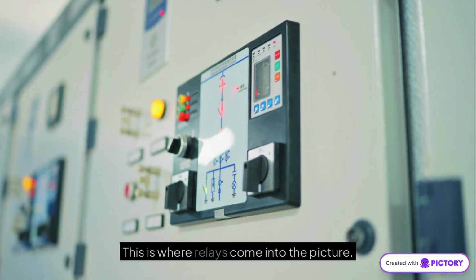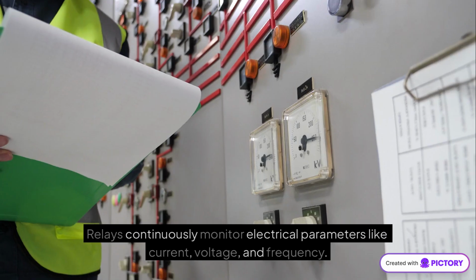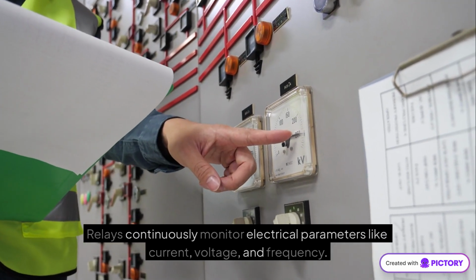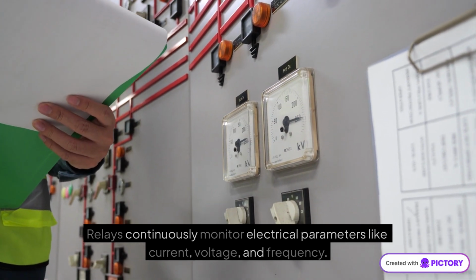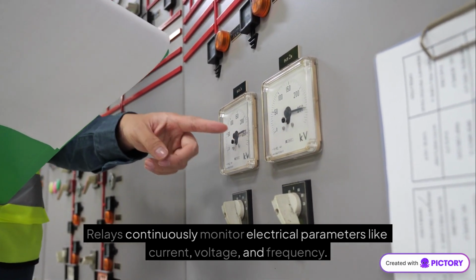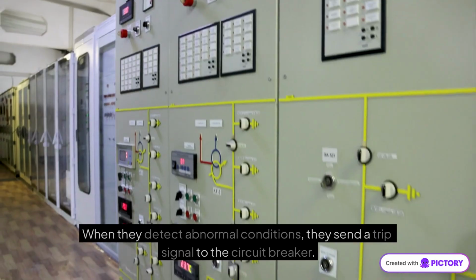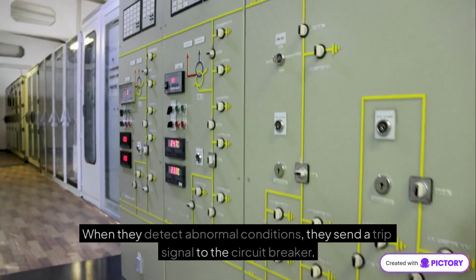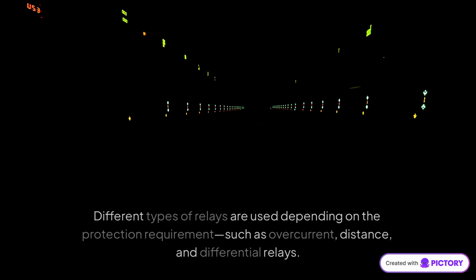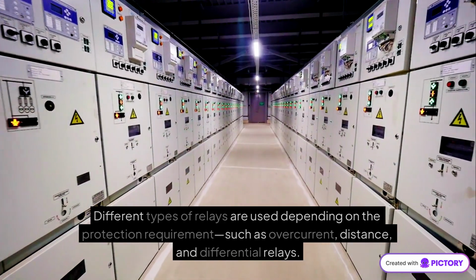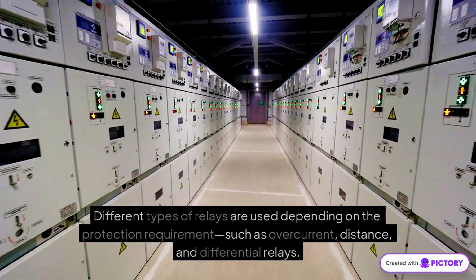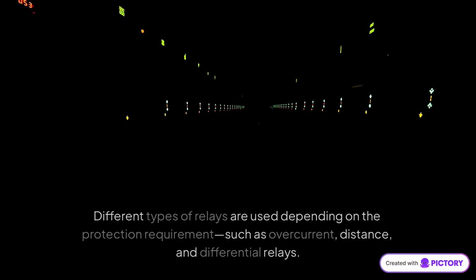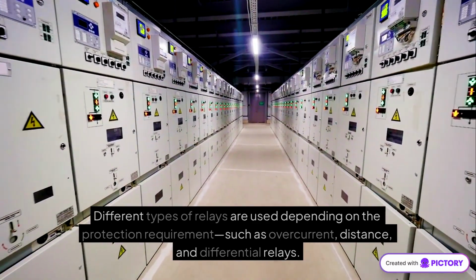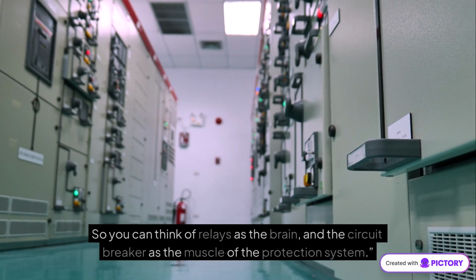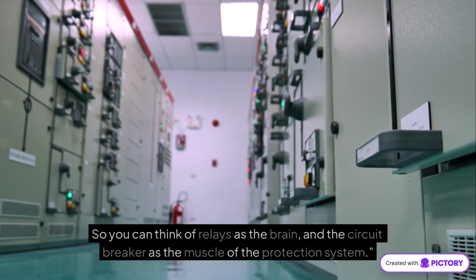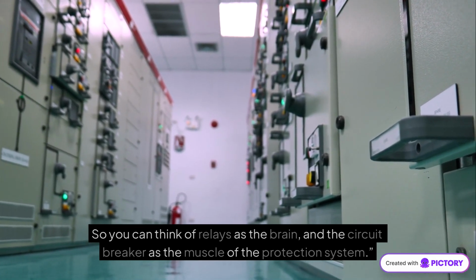This is where relays come into the picture. Relays continuously monitor electrical parameters like current, voltage, and frequency. When they detect abnormal conditions, they send a trip signal to the circuit breaker. Different types of relays are used depending on the protection requirement, such as overcurrent, distance, and differential relays. So you can think of relays as the brain, and the circuit breaker as the muscle of the protection system.